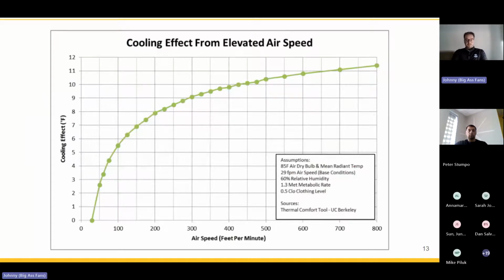This has been mapped out by others—ASHRAE, University of Cal Berkeley's Thermal Comfort Tool. What we have here is an example of what would likely be an office environment, based on the assumptions in the bottom right. You can see as we elevate the airspeed in feet per minute along the bottom axis, the cooling effect in Fahrenheit is rising. So as an example, in an office you might shoot for 120 feet per minute, because we've tested at our R&D lab that papers start to flutter after that point.